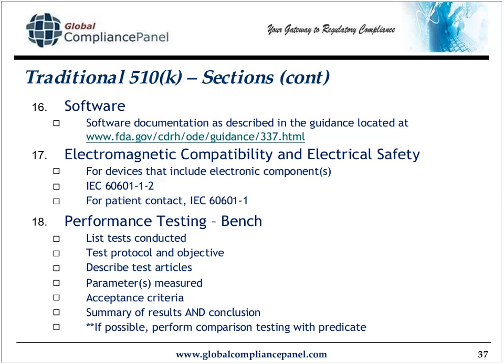Therefore, the longer and more in-depth it is, the more appreciative the reviewer is to look at a summary of the results and a conclusion saying that the device is safe and effective. If you can get a predicate device, if it's yours, you certainly can. If it's your customer's, sometimes you can use maybe a friend of your company that you can fund to buy a handful of the competitor devices, the predicate devices. The reviewers really like it when you perform comparative performance testing between your device and the predicate device.